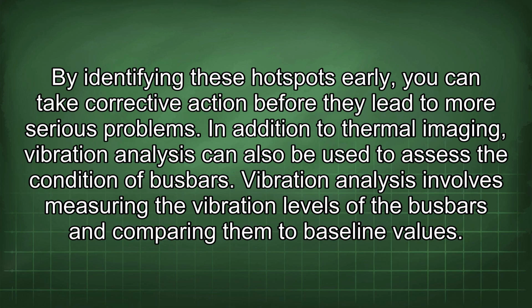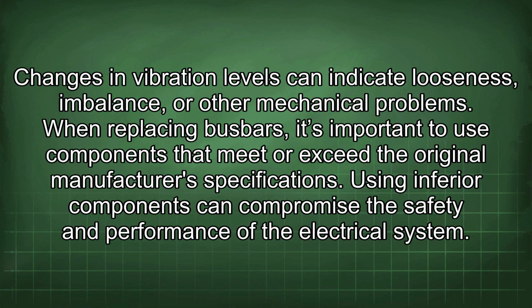In addition to thermal imaging, vibration analysis can also be used to assess the condition of busbars. Vibration analysis involves measuring the vibration levels of the busbars and comparing them to baseline values. Changes in vibration levels can indicate looseness, imbalance, or other mechanical problems.